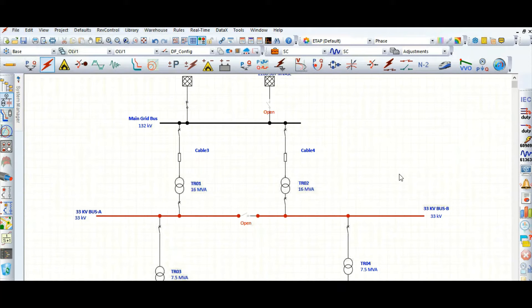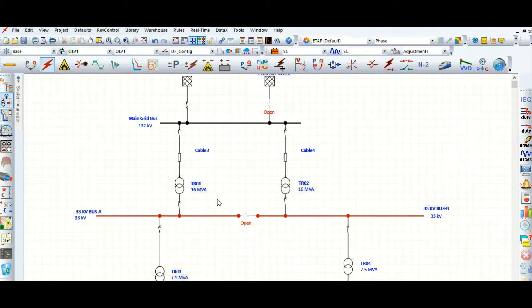This video covers how to represent the transformer neutral grounding system — whether it is solidly grounded, resistance grounded, or reactance grounded — and how to assign the NGR values for the transformer. We'll understand why it is required to restrict the single line-to-ground fault at different voltage levels, and how the neutral grounding resistor is used to calculate the LG fault current.